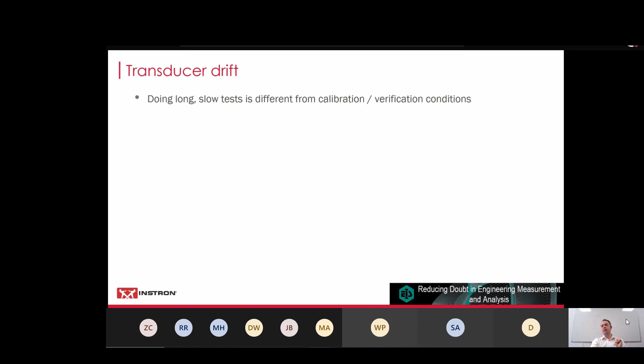And this is why, once again, mechanical testing laboratories should be reasonably temperature controlled. Because a few degrees difference can be enough to shift the zero point on your measurement, or it can shift the overall full-scale reading. So once again, for the people at the back, use a transducer with a sensible range. Let me give you a common fatigue testing example on this.